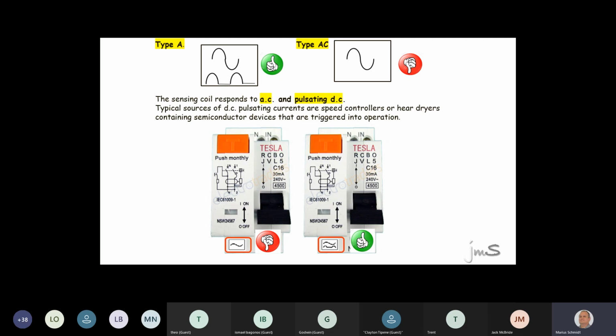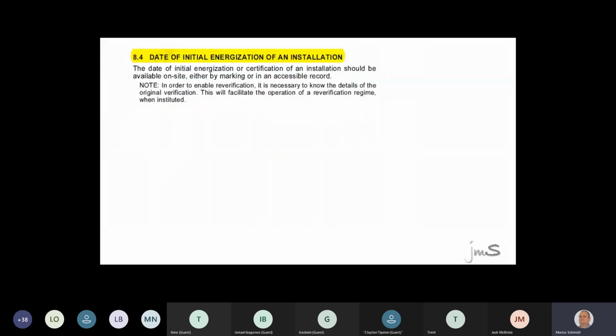Now guys, if you import any Australian fitting like a caravan or a boat which has power on it, you'll see they all come to New Zealand with an AC only. Then what we need to do, we have to change it. You guys happy with that? Cool. Right guys, when we talk about RCDs, do you know the times in which RCDs must operate? 30 milliamps, 30 milliseconds. 300 milliseconds. If you up it 5 times, it becomes 150 milliamps within 40 milliseconds. Where will I get all that? Regulation number 24. All the times that are in there.